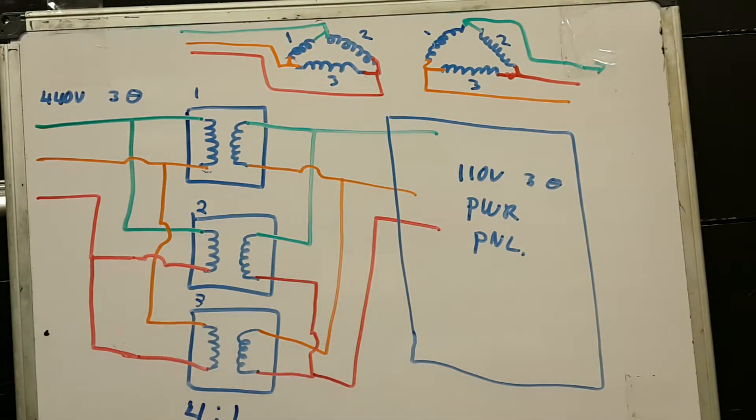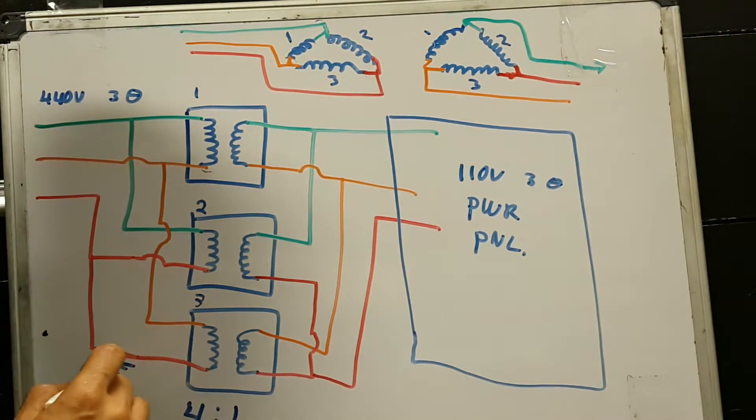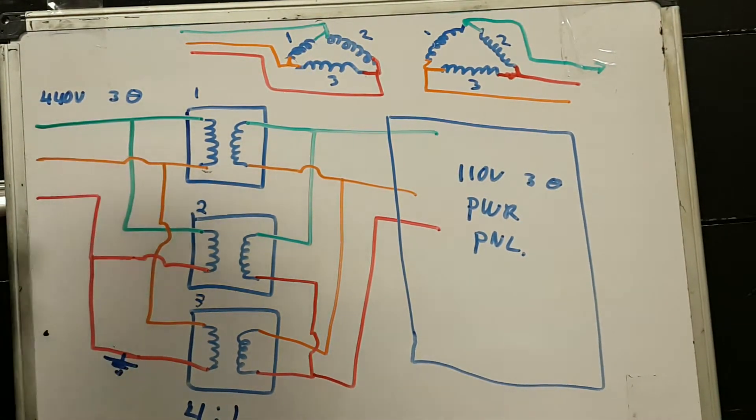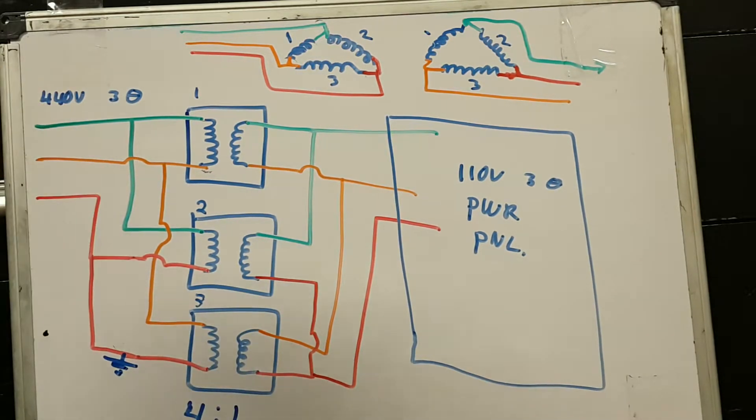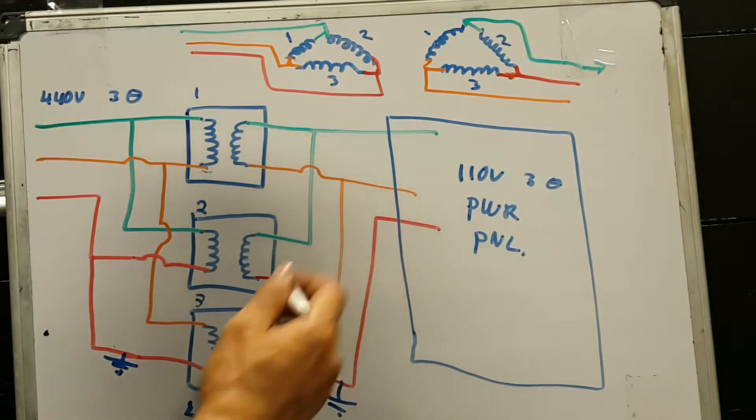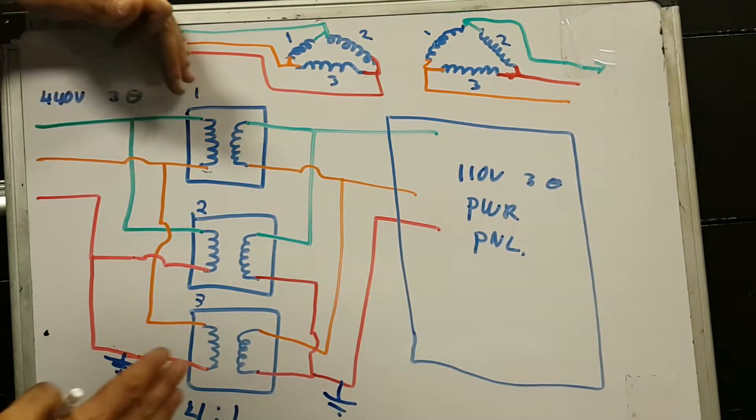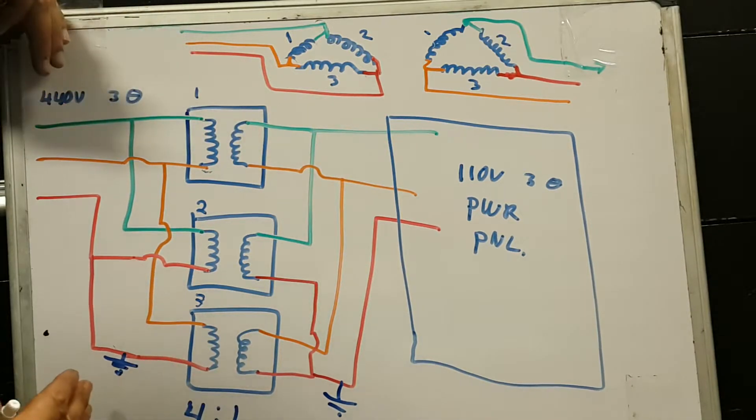Now, keep in mind that if I get a ground here, I would be able to detect it in the 440 three-phase distribution system. But if I get a ground here, it would be invisible from this side, from this side of the distribution system.